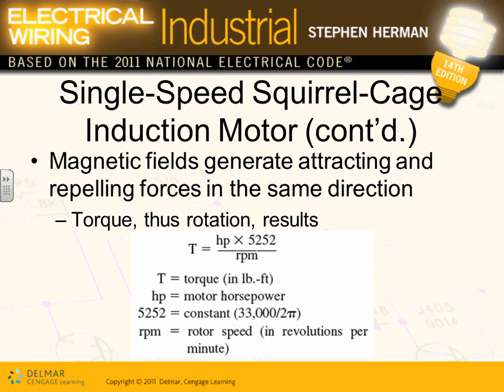Why? What do you do with the torque? You make things spin at a certain force, right? So that's one of the most important things. The way we find the torque is we take the horsepower that you designed the motor for, multiply by this magic number 5252, and divide by the RPM of the motor. Can you guys see what happens if you slow your motor? The speed is lower, the torque goes higher. Can you see that?